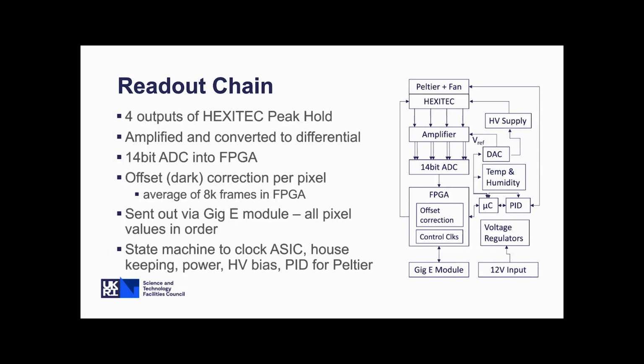So we have a 14-bit ADC, and that goes directly into an FPGA, which is on the board next to the detector. That FPGA takes those peak hold voltages, the energy per pixel value, and does a dark correction per pixel. That's done automatically in the FPGA, as is measuring the offset values per pixel. It takes an average of 8,000 dark frames and stores them locally on the FPGA, and they're subtracted as the data is read out. It comes out on a GigE module here, so it's just a standard GigE protocol. It just plugs into your PC or your laptop, and it's ready to go.